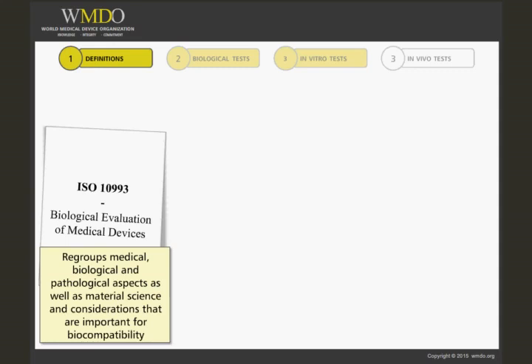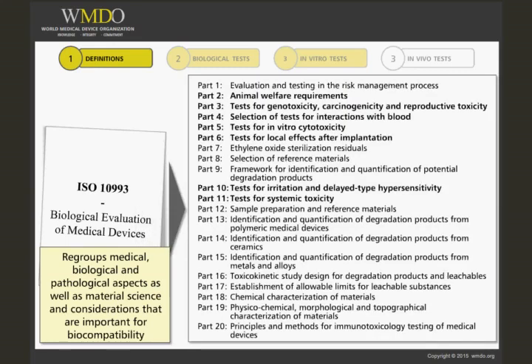The biocompatibility tests recommended in various parts of ISO 10993 are based on models such as bacteria, mammalian cell lines, and animals that are far from clinical reality, but are prerequisite to any clinical trials.